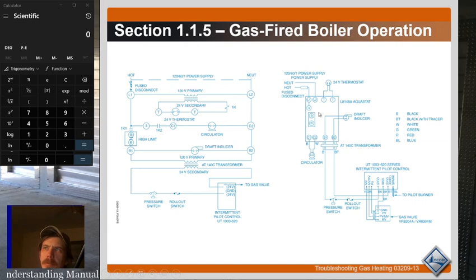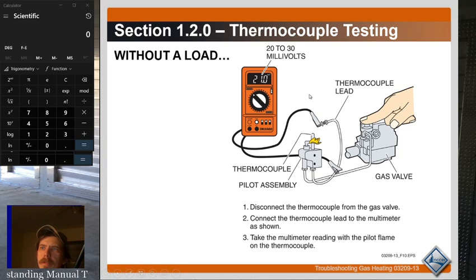Here's a gas-fired boiler wiring diagram. Typically, gas-fired boilers are going to have the same sequence as any gas furnace, but I will say boilers seem to more commonly be either a standing pilot or an intermittent spark ignition. Hot surface igniters are slightly less common, but it could be any of those three. It doesn't really matter. Every boiler is kind of its own animal, but they're generally extremely simple.